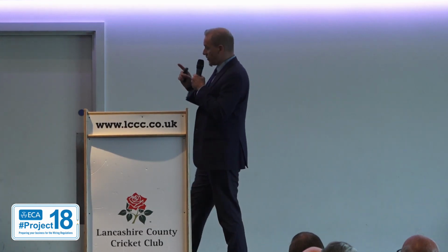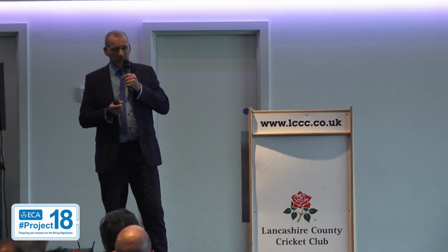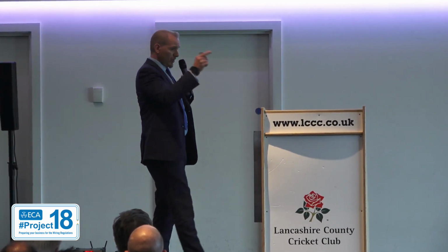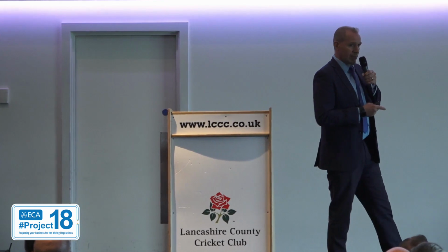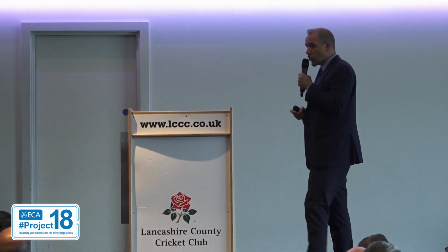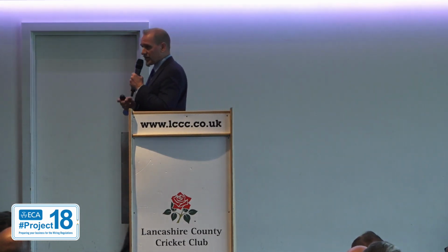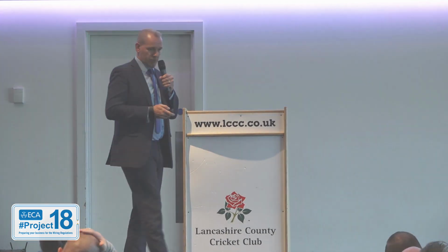So previously, before the CPR regulation, you could request a certificate of compliance from a manufacturer. That's effectively just an A4 letterhead with a company stamp in the corner that says, I as the manufacturer declare that my product complies with the standard. That's all it says, nothing else. The declaration of performance that accompanies a cable now under the CPR has to have all of the technical information. So it's just a pointer to take away.